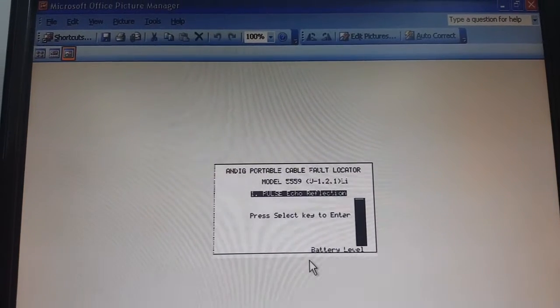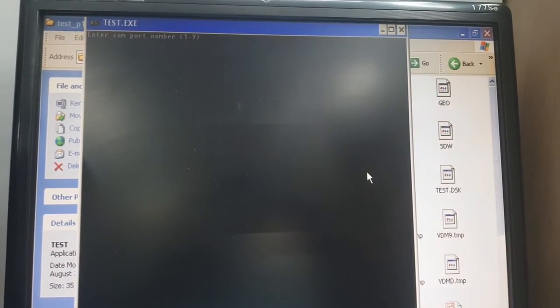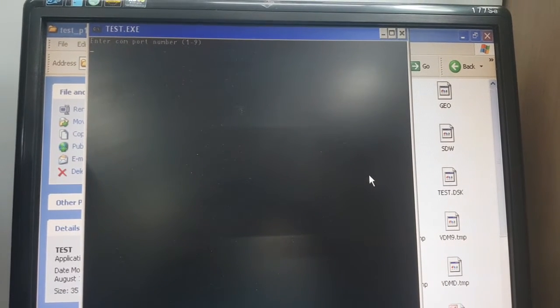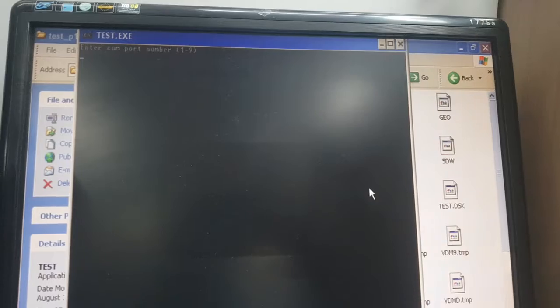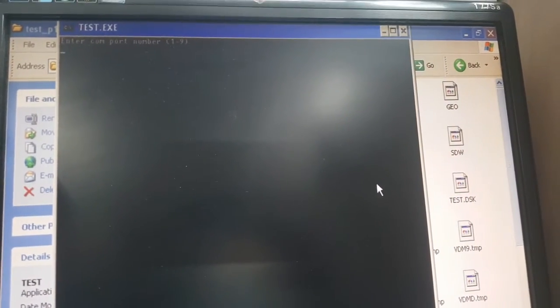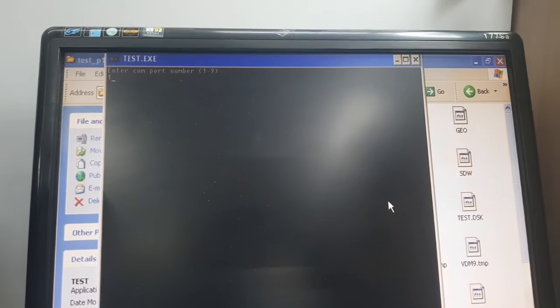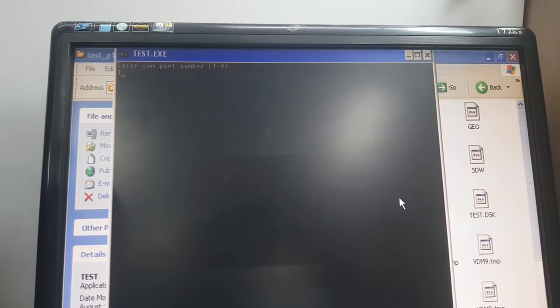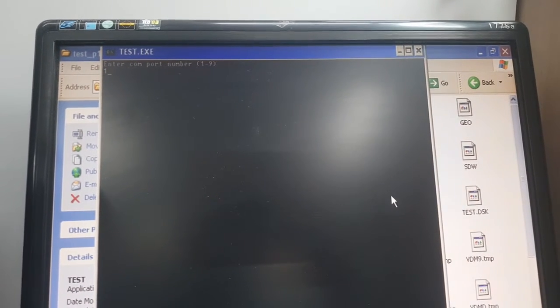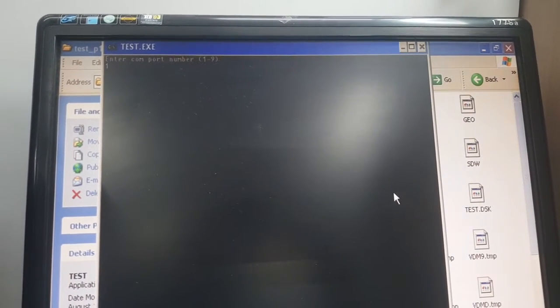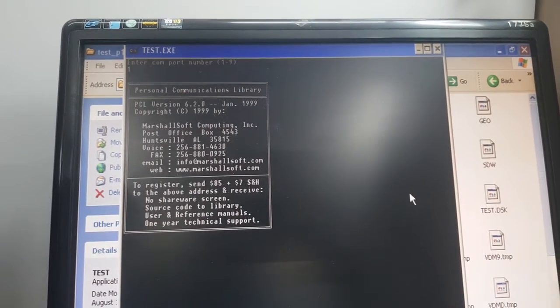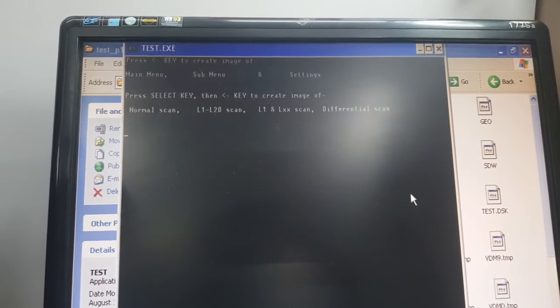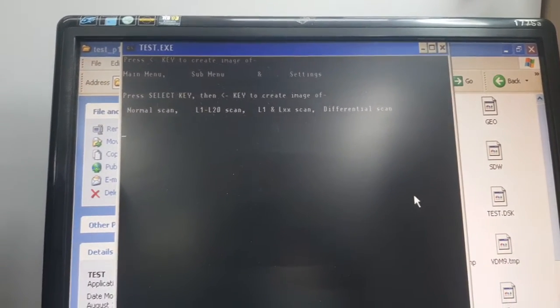To take the screenshot of the waveform, again click on test p1, go to test.exe and open the file. Enter the port number one. We have connected to port number one. Please note you can connect anywhere between port number one to port number nine. Please enter the port to which you have connected. Press enter, press enter again. Now if you want the screenshot of the waveform, you have to press select key and then the left arrow button.